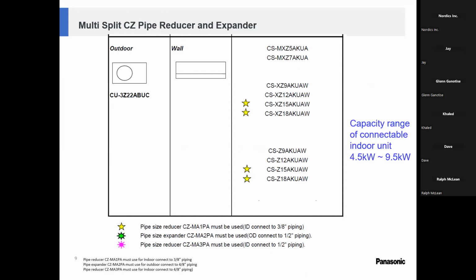So as you can see here, capacity range of connectable indoor units is 4.5 kilowatts to 9.5 kilowatts. If you want to convert that to BTU per hour, it's 3,142, if I'm not mistaken, or 3,412. I could be wrong. It could be the other way around. But anyway, please remember, when you're doing a multi-zone, always respect minimum and maximum capacity. If you put less than required, you will get an error of H12. And if you put more than required, you will get an H12 as well. And if you want to know what is H12, download the app, please.